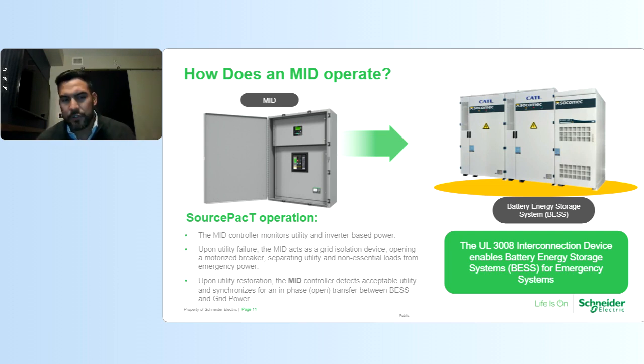Additionally, once utility is restored, let's say you're on emergency power mode with your energy storage system, SourcePacT, the controller, will detect that utility has returned. So it enables a safe transition back to utility. Once the controller senses that utility is present, the controller will send a signal to the energy storage system or the energy management system in charge of the microgrid, instructing the system that utility has returned. It will tell those inverters to shut down, to basically go into grid tied mode again. We're operating in grid interactive mode, we're connecting back to the utility. It will close that breaker, and then your microgrid or your battery storage system is operating in grid interactive mode, back under normal conditions.